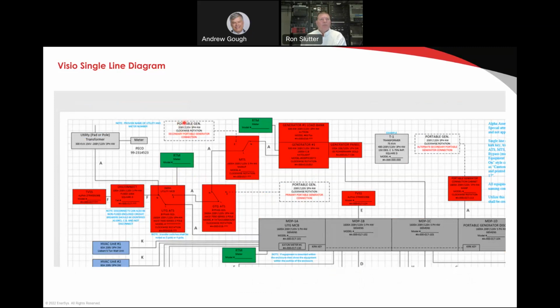So if I brought a portable generator in and I needed to connect to a system, we would typically do that to a maintenance manual transfer switch. Okay, and then that allows us to connect the portable generator and then transfer to it very quickly without any downtime. So that's very, very important when you're doing maintenance activities. Maybe when your fixed generator went down, you can do that in different locations and under different pieces of equipment and different connection points. So it's very helpful to know where you can connect a portable generator.